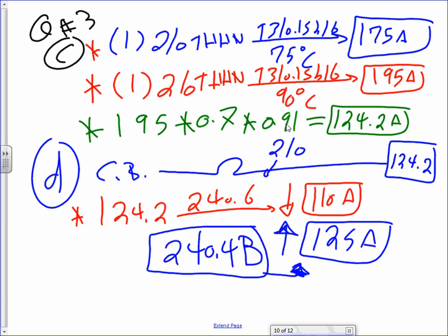Any comments, guys? Any questions? So I can go down to 110 amps because 124 is not a standard breaker size. So I'm going to size it based on the 110. This will be a 110 amp circuit breaker, 2/0 AWG, and it limits my load, which is 124, so this one is lower than 124. If you put a 110 circuit breaker, can you pull 124 amps out of it? You can't. This will trip.